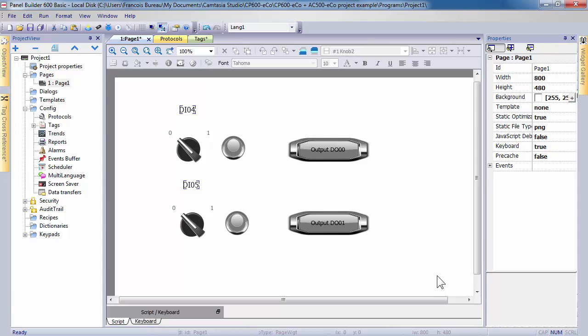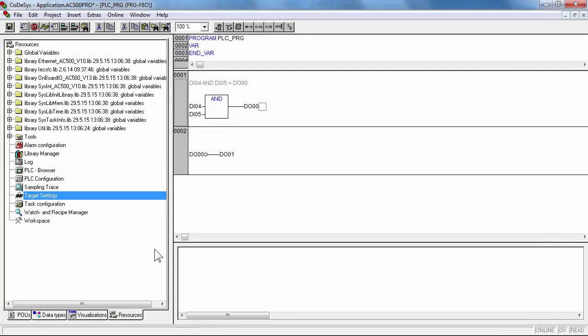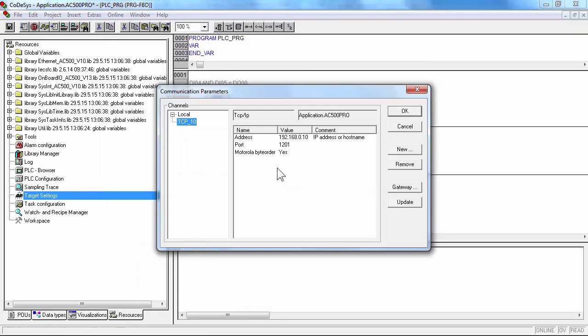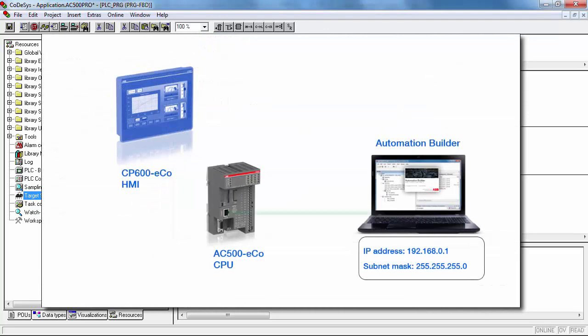An HMI simulator tool allows you to test and debug your application before downloading your application to the CP600 ECO panel, or if you don't have panel available. In order to test and demonstrate your complete project with AC500 ECO plus CP600 ECO, you need to download in both the devices their respective project. Start by AC500 ECO CPU, and from IEC 61131 application. Verify that the communication parameters are according to the IP addressing of your CPU. Connect the Ethernet connection between computer and CPU.